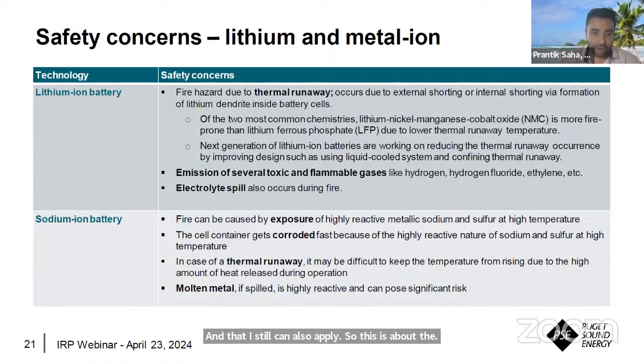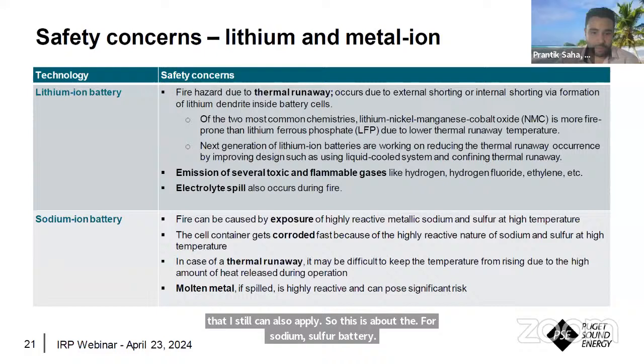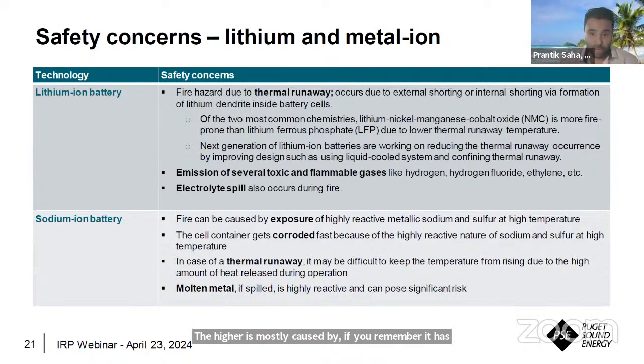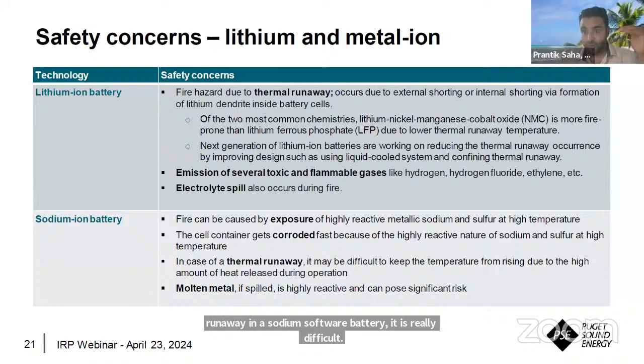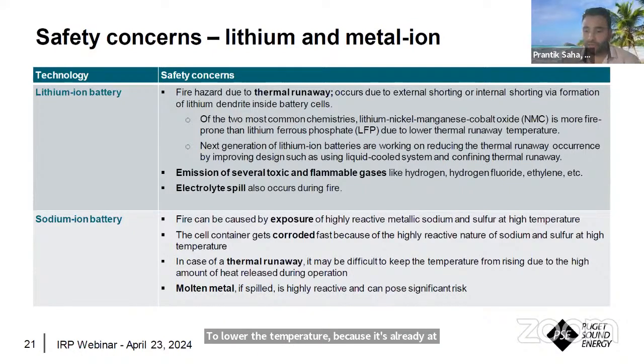For sodium sulfur battery, the fire is mostly caused by the molten sulfur and molten sodium it contains. If they get exposed, being highly reactive metals, they oxidize very easily and cause fire. Because of their high reactive nature, they corrode the walls very fast, although there have been R&D developments and we're seeing much better performance over the last 2-3 years. Also, in case of thermal runaway in a sodium sulfur battery, it's really difficult to lower the temperature because it's already at 300 degrees Celsius and highly reactive, so thermal runaway events can get out of hand very quickly. These are the major safety concerns for lithium-ion and sodium sulfur batteries.